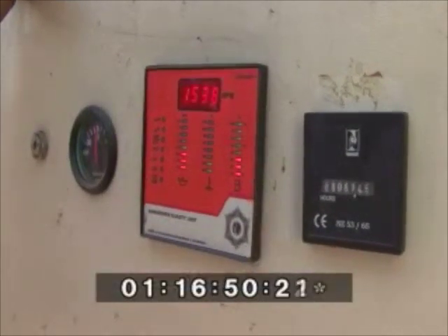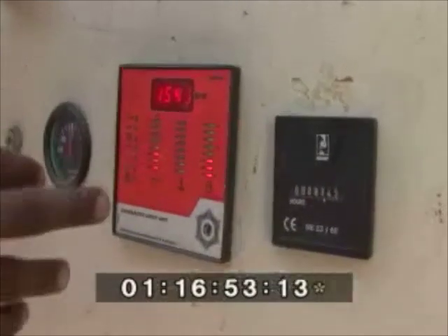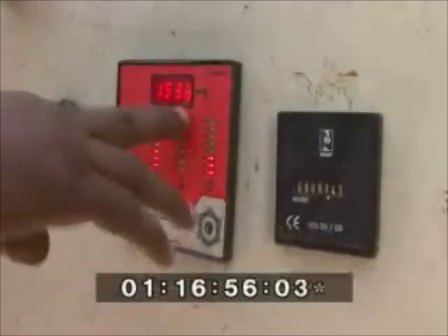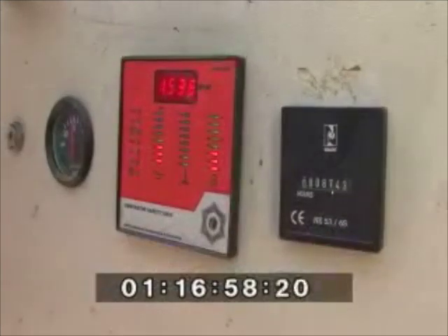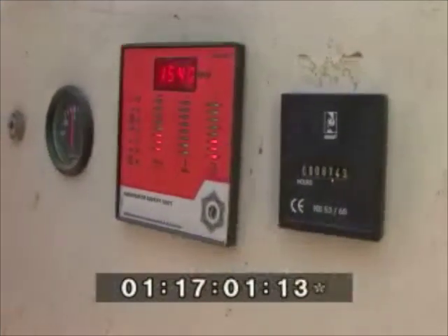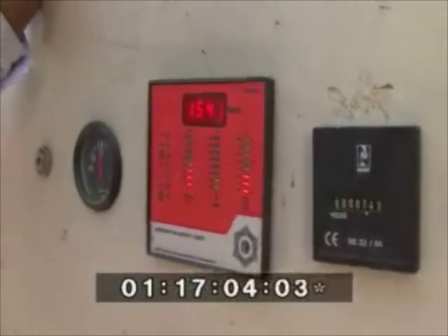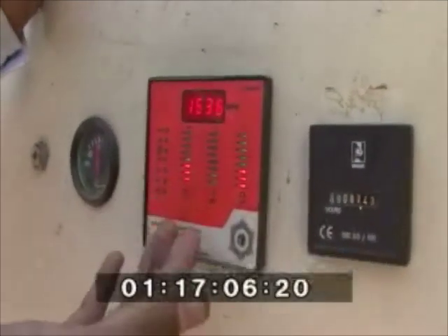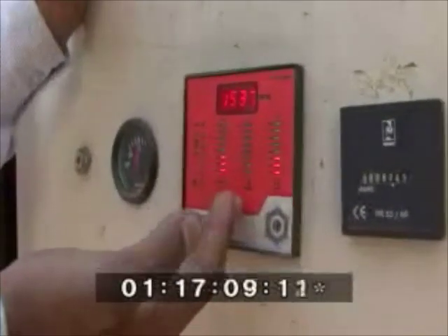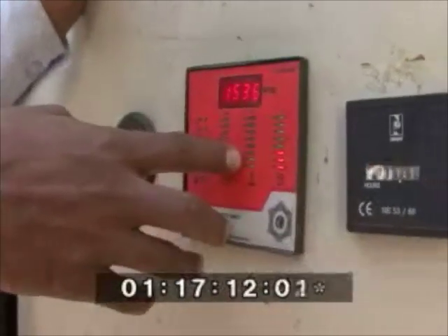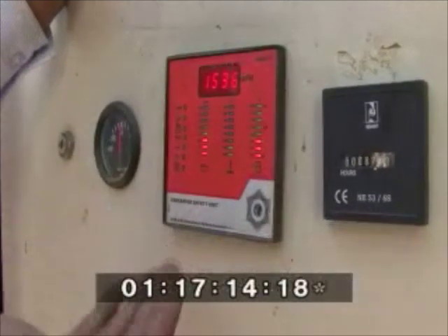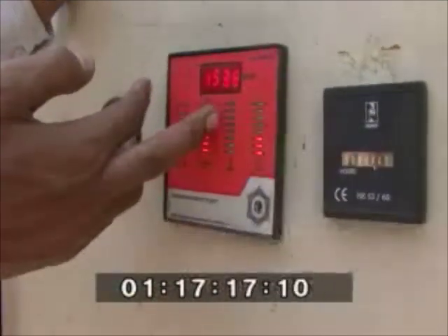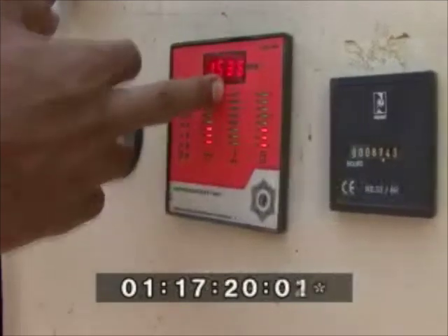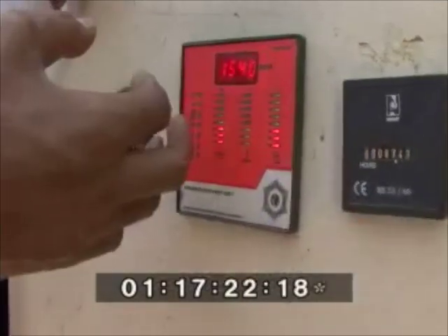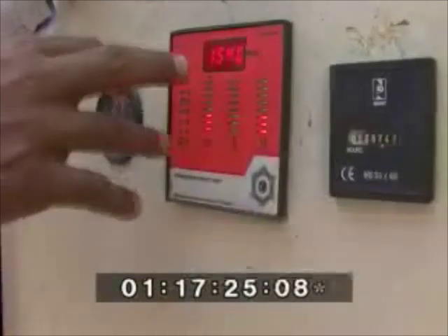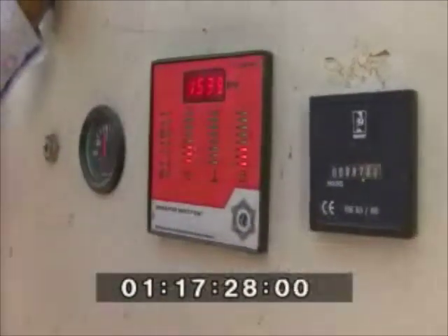Now we are seeing the HCT meter. This meter is connected to the HCT sensor. Now it is showing 15 degree centigrade. Slowly the temperature will start rising with time while the DG is working. Once the temperature reaches the 110 degree mark, the DG will be switched off. This is for the safety of the DG.